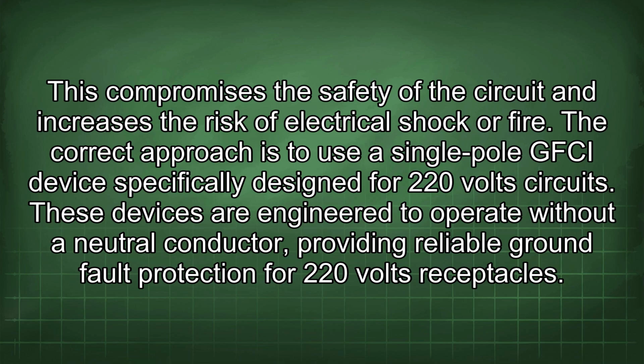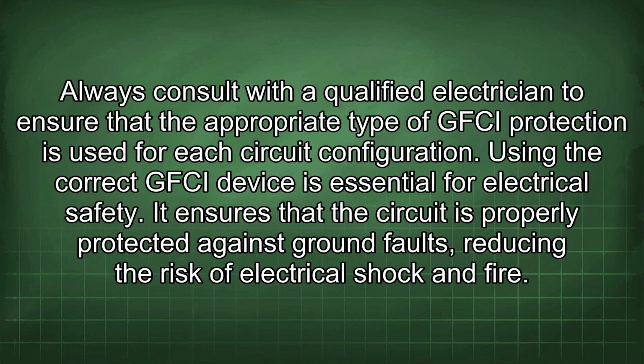The correct approach is to use a single-pole GFCI device specifically designed for 220-volt circuits. These devices are engineered to operate without a neutral conductor, providing reliable ground fault protection for 220-volt receptacles. Always consult with a qualified electrician to ensure that the appropriate type of GFCI protection is used for each circuit configuration. Using the correct GFCI device is essential for electrical safety.